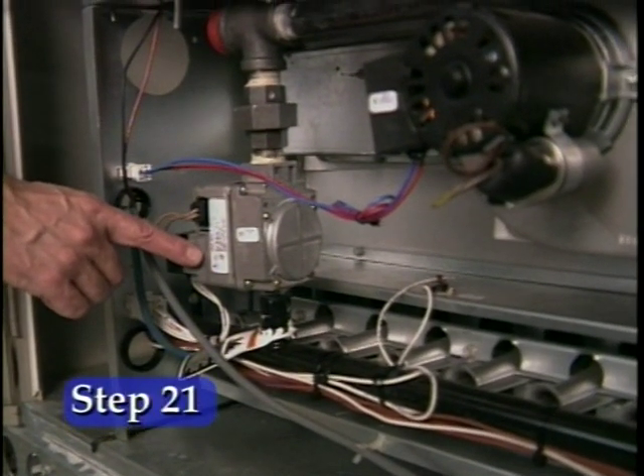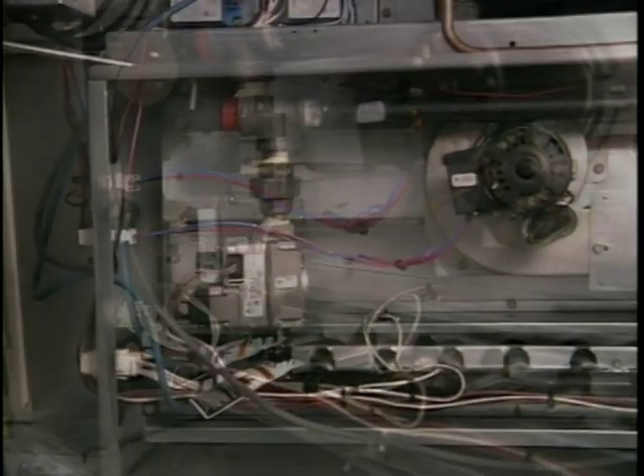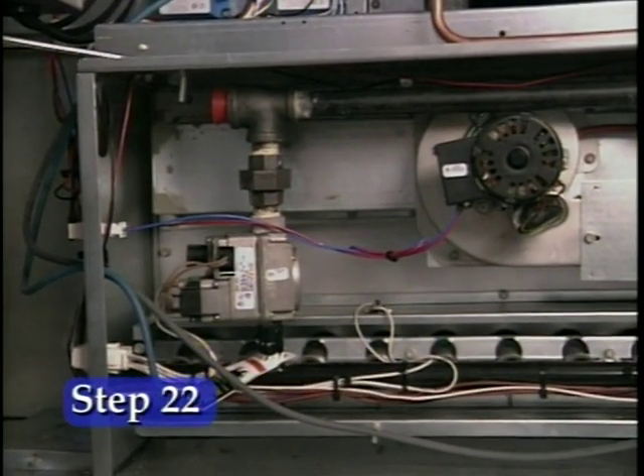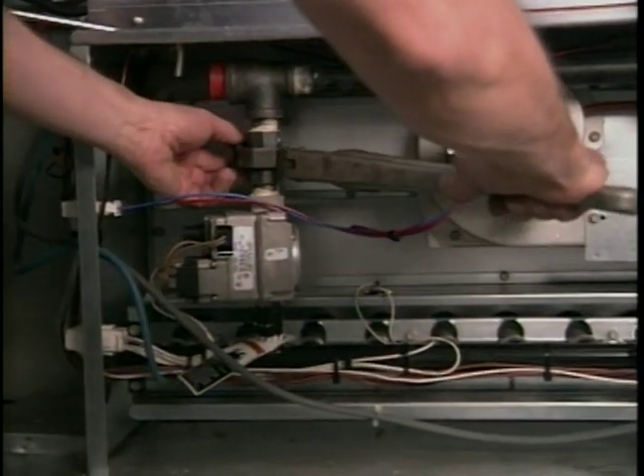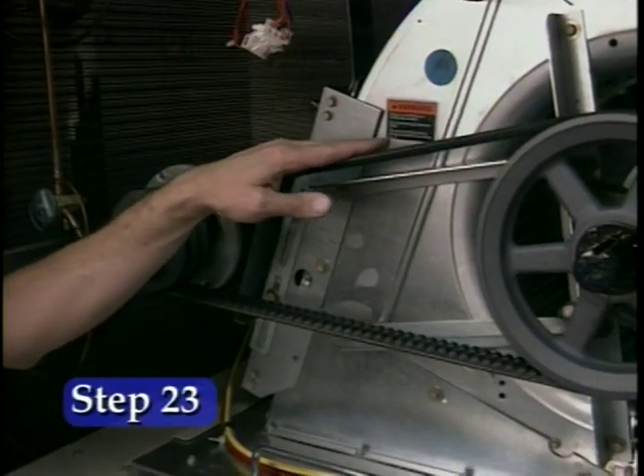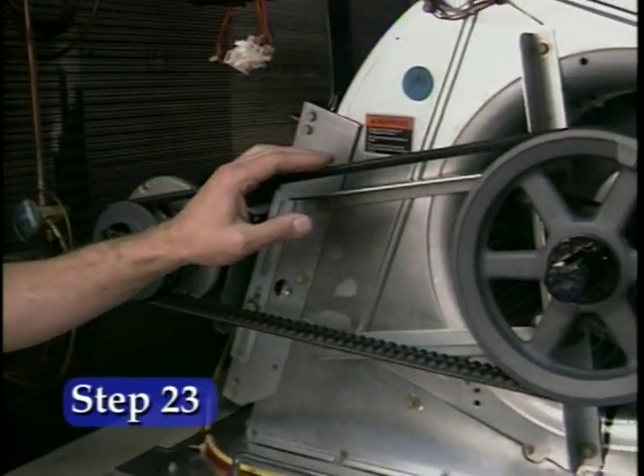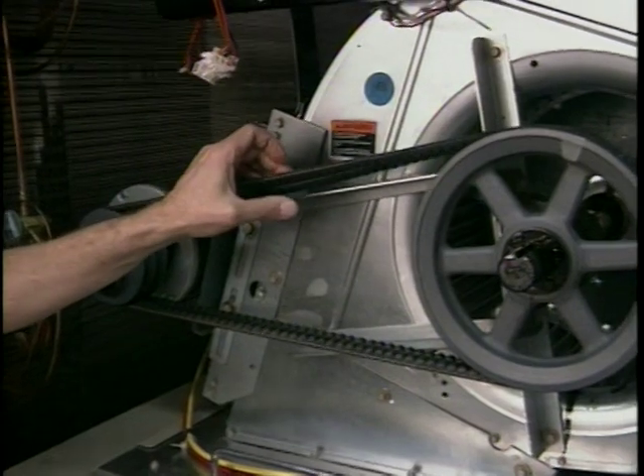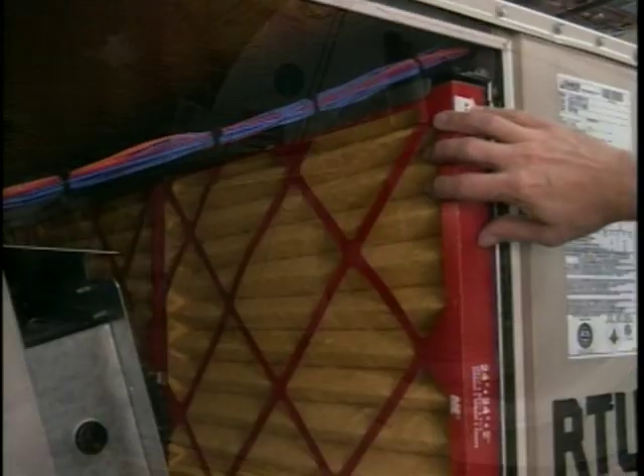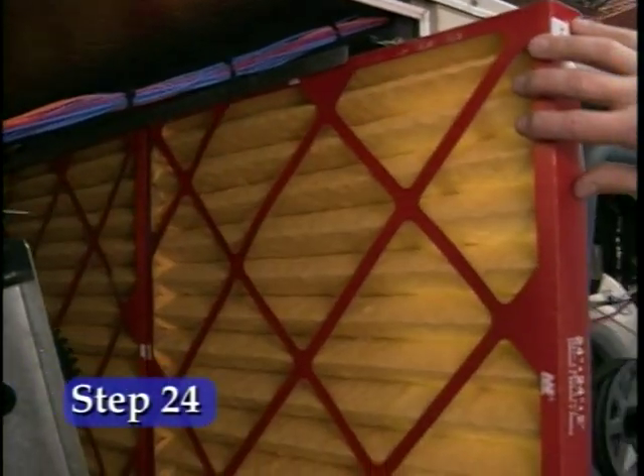Note and record fuel type. Check gas train unions with a wrench. On electric-only units, check NA. Visually inspect the belt tension and alignment. On multi-belt drives, check that all belts are installed. Visually inspect the filters.